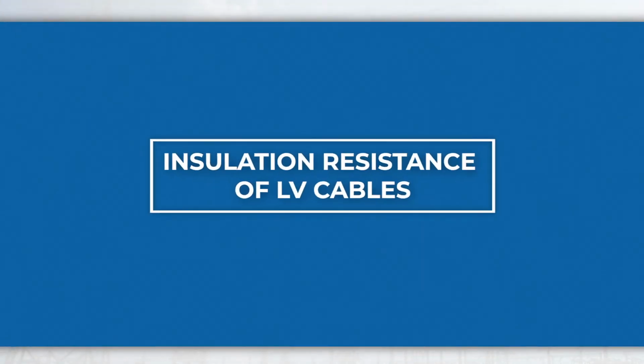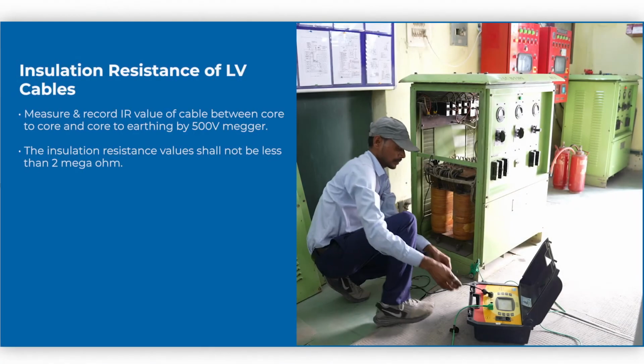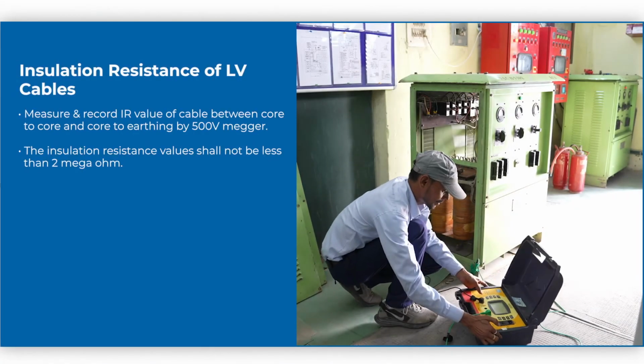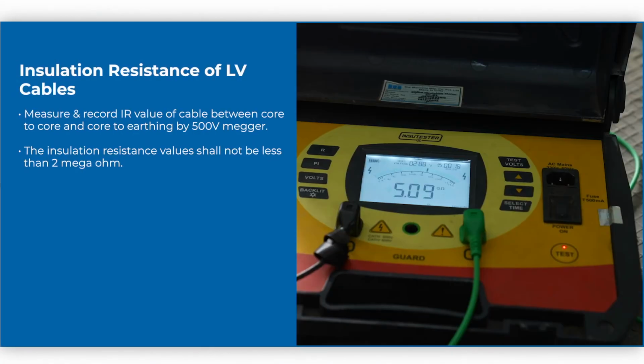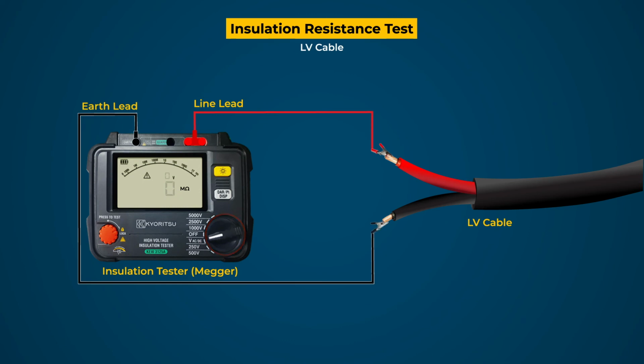Insulation resistance of LV cables. Measure and record IR value of cable between core to core and core to earthing by 500 volt megger. The insulation resistance values shall not be less than 2 megaohm.